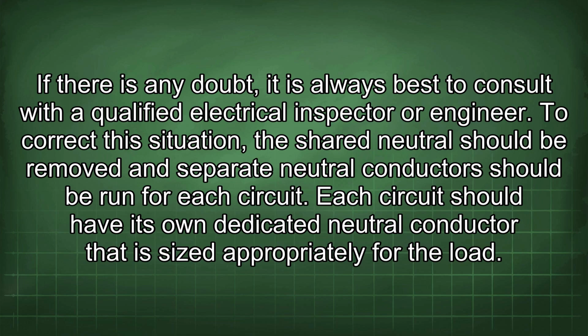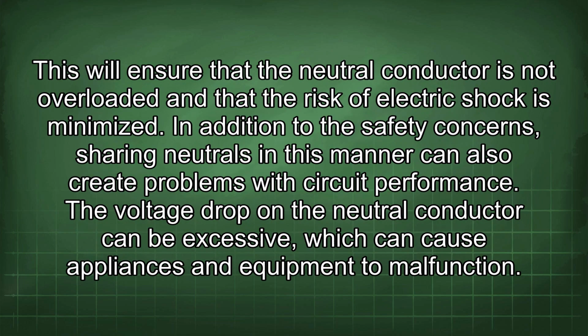To correct this situation, the shared neutral should be removed and separate neutral conductors should be run for each circuit. Each circuit should have its own dedicated neutral conductor that is sized appropriately for the load. This will ensure that the neutral conductor is not overloaded and that the risk of electric shock is minimized.